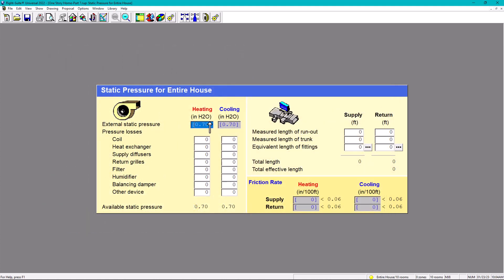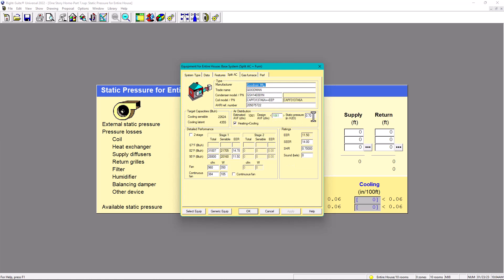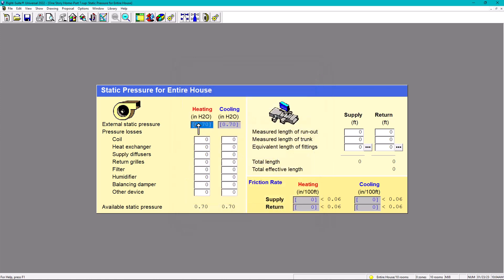We're starting with 0.70 external static pressure. However, many contractors would say we should size it at 0.5 static pressure. What happens is that if we put 0.5, we're not going to have enough available static pressure, or you're going to need a bigger filter. So let's start with 0.7 external static pressure. Now we have pressure losses - we have basically 8 pressure loss categories.